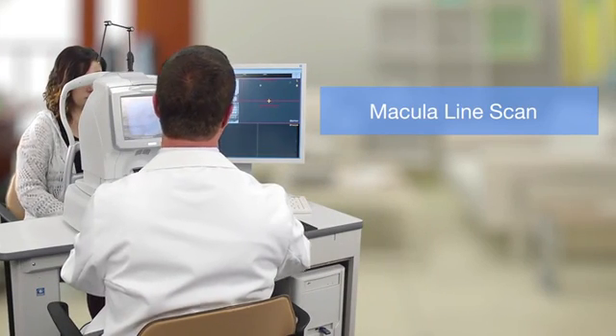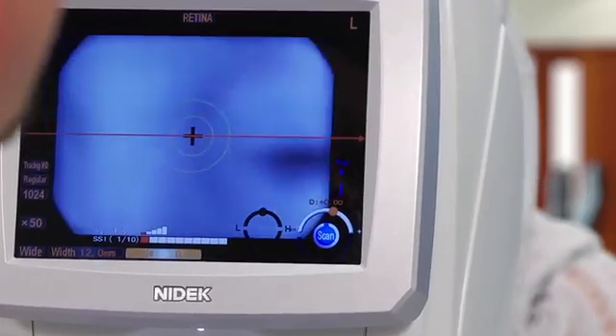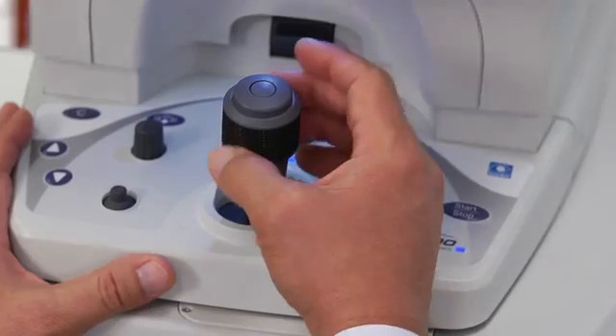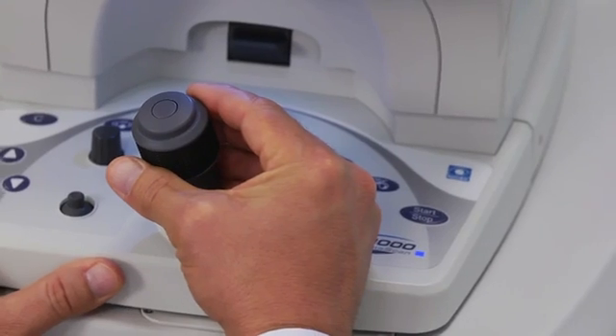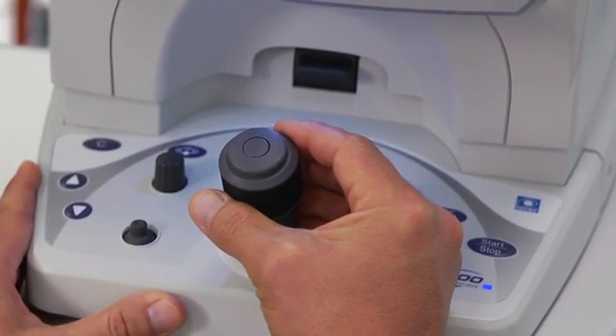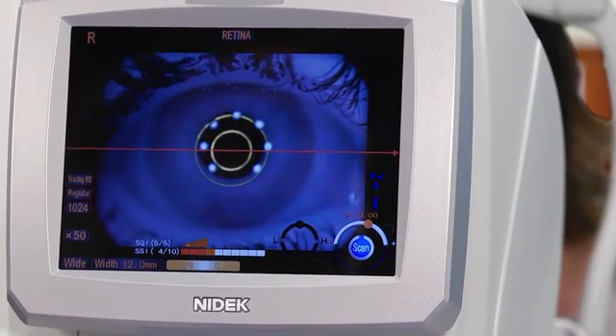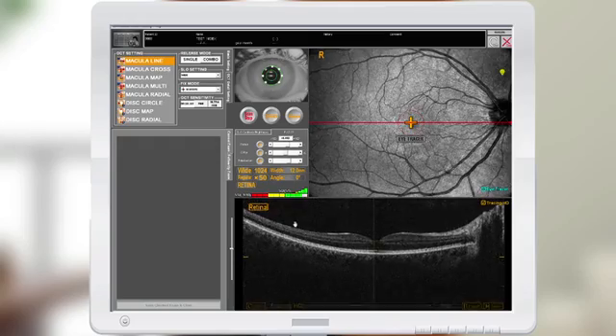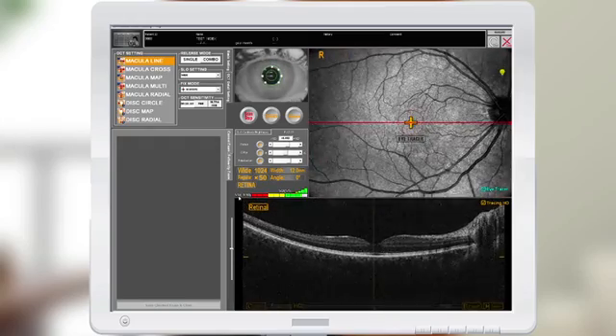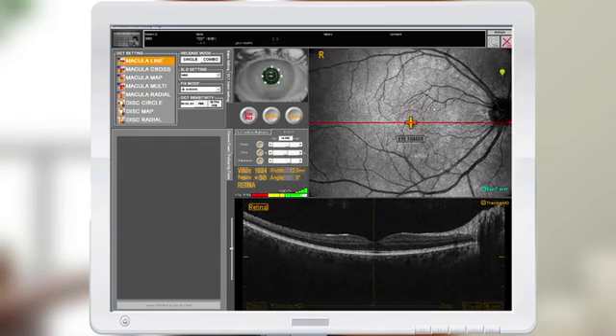I'm going to demonstrate how to take a macula line scan. Angela, please put your chin in the chin rest and your forehead against the forehead rest. Adjust the OCT and the chin rest so the circle is outlining the patient's pupil. Slowly move the main body toward the patient, keeping the circle concentric with the patient's pupil. Evaluate your signal strength index and your signal quality index — the quality index reflects the quality of your SLO image.